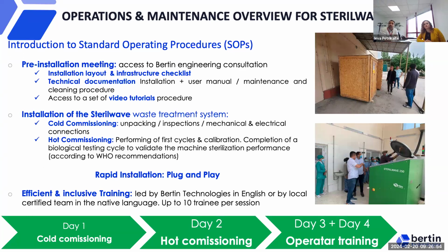Then we do the hot commissioning. We perform the first cycle with the operator of the hospital, and we complete biological testing to validate with the end user that the machine performs at its nominal condition, according to World Health Organization recommendations. So it's really a simple, plug-and-play machine, 1-2 days for the full installation.